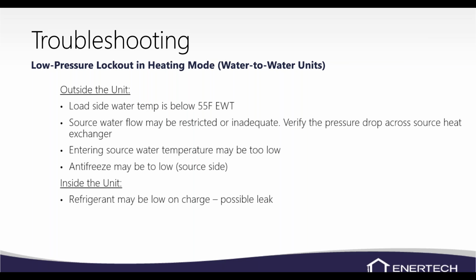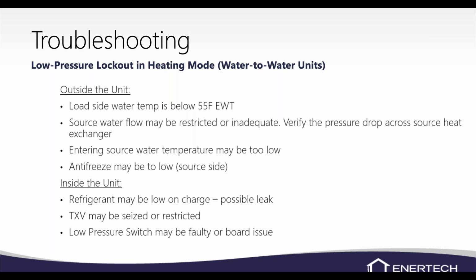Inside the unit, obviously low on refrigerant. If it is low on refrigerant, check for a leak. It didn't come from the factory low on refrigerant. It's impossible for it to leave the factory without a proper charge in it. Now, in shipment, it could rattle around and cause a leak, but just know that it didn't leave the factory with no refrigerant in it. Again, TXV restricted or seized, and low pressure switch or a board problem.